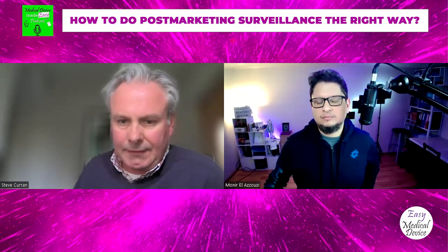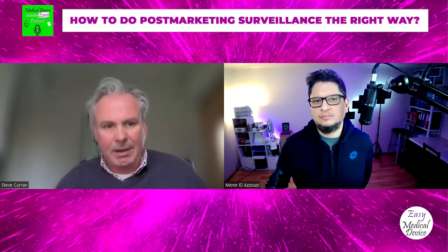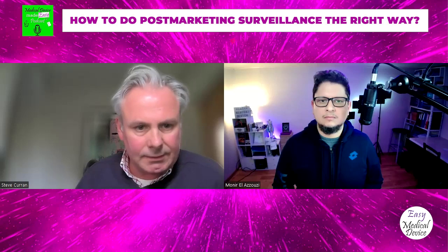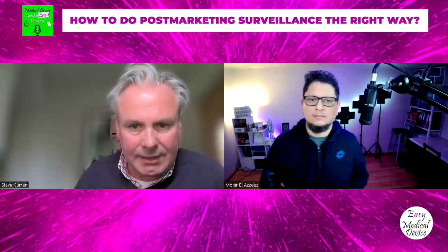Yeah, they'll certainly, like I explained with that example, the auditors from the notified body will be experts in that area. They'll be experts in orthopedics and understand those devices very well. They'll obviously take account of looking at all the documentation that a manufacturer has. So that's the point, that all of this has to be properly documented with proper rationales and proper justification and understanding of how this data is applicable to the market that the manufacturer is seeking approval in.